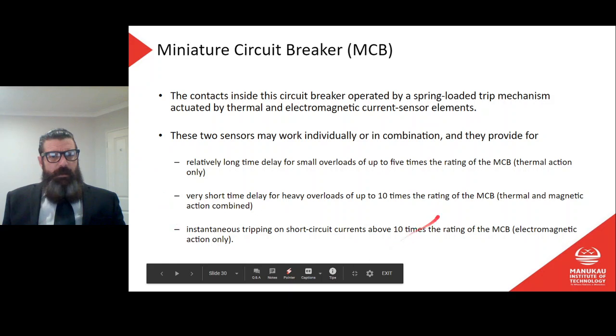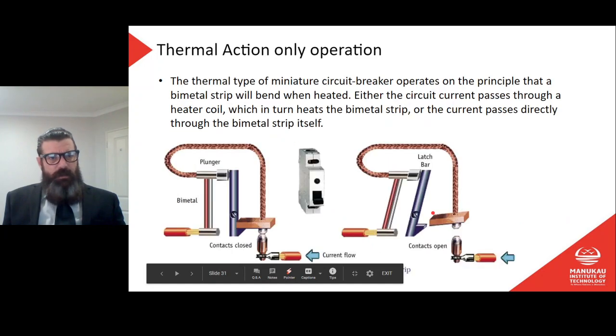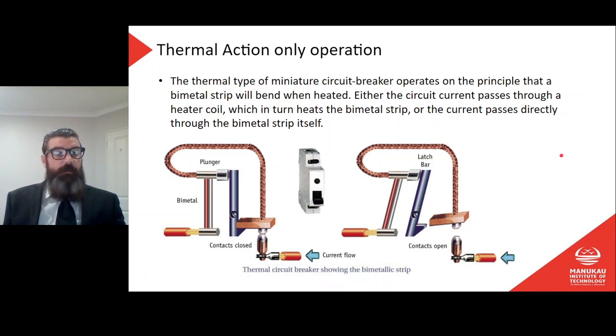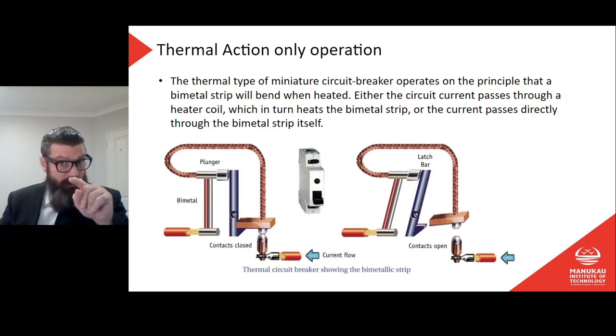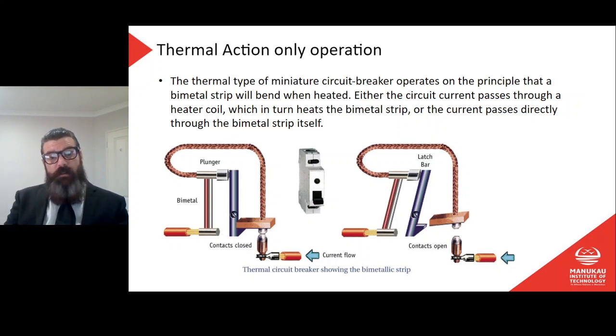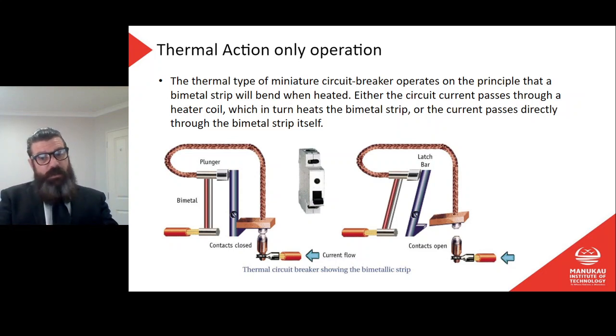Okay, so we've got here information about the two types of tripping mechanisms, which we have talked about. I won't go into that again. Okay, so here's our thermal action. Let's have a look at this. The thermal type of MCB operates on a principle that the bimetal strip will bend when heated. That's the same as what's happening in a thermostat, various other things. We've come across this concept a lot, right? Either the circuit current passes through a heater coil, which in turn heats the bimetal strip. So the current in the circuit is heating a small coil, which will heat the bimetal strip. Or the current's going straight through the bimetal strip, which will heat the bimetal strip by itself.